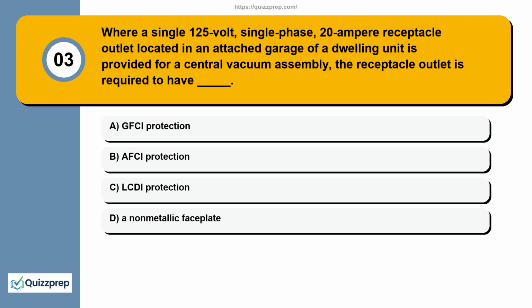Question 3. Where a single 125-volt, single-phase, 20-ampere receptacle outlet located in an attached garage of a dwelling unit is provided for a central vacuum assembly, the receptacle outlet is required to have: GFCI protection, AFCI protection, LCDI protection, a non-metallic faceplate.